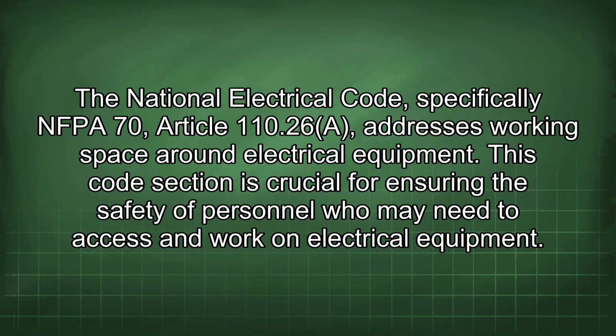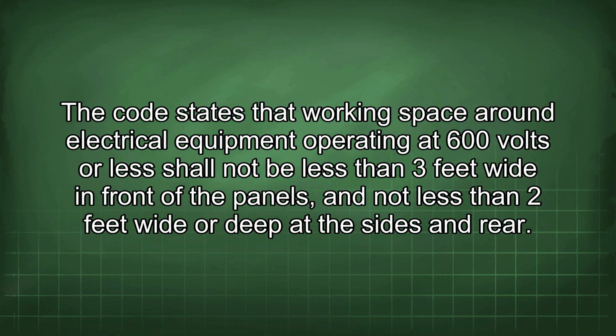The National Electrical Code, specifically NFPA 70 Article 110.26a, addresses working space around electrical equipment. This code section is crucial for ensuring the safety of personnel who may need to access and work on electrical equipment.